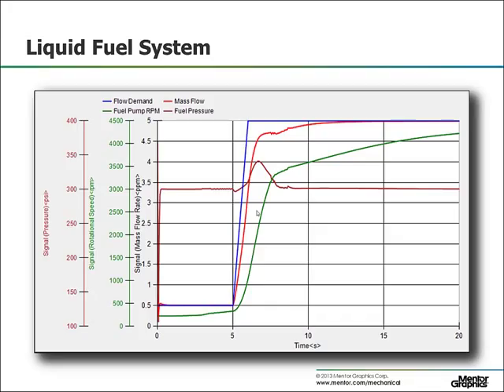We have plotted pressure to show you how the pressure control system and bypass system is able to cope with the changing pump speed and hold on to a consistent 300 psi set point. Like with the other systems, the performance of the pressure control is determined by the P, I, and D coefficients inside the controller that we supply, as well as the sizing of the bypass line and valve that again was done in earlier simulations.